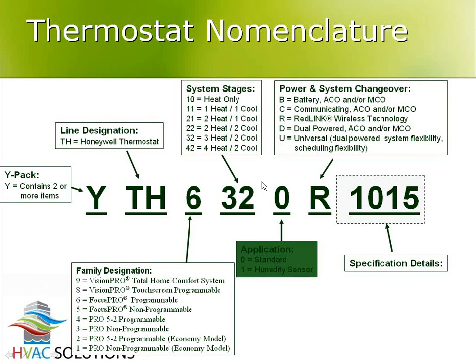the Vision Pro IAQ. The next digits indicate the staging of these. So the first one is heat, the second one is cool. So this is a 32. So it's 3-stage heat, 2-stage cool in this example. The 0 means it's a normal stat. 1 would mean it has built-in humidity control on it. Then that next digit, the number there, is the series that it is. So B means it's a battery stat. C means it's a communicating stat. R means it's a wireless RedLink communicating stat, and then so on down the line.